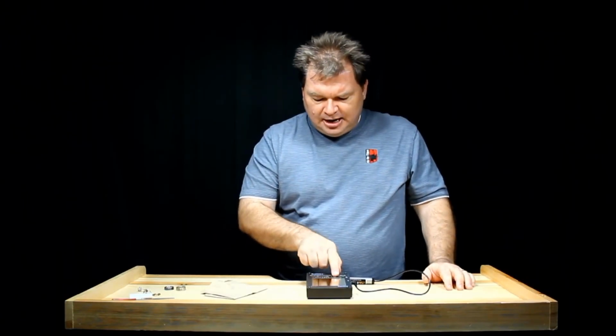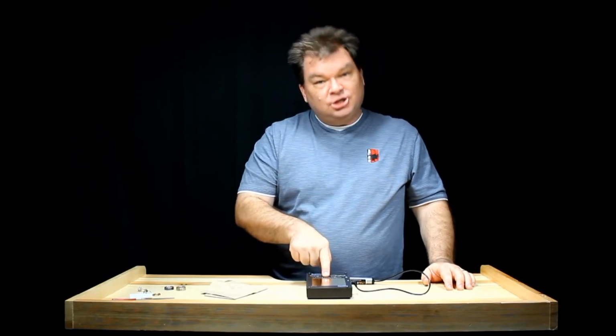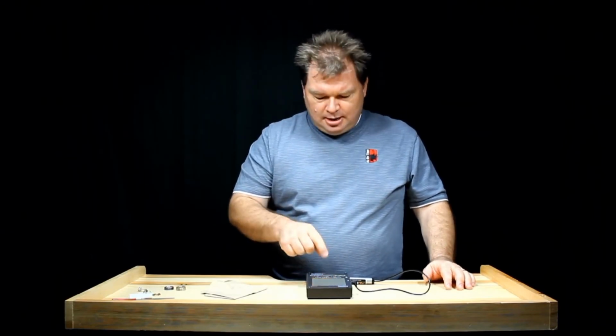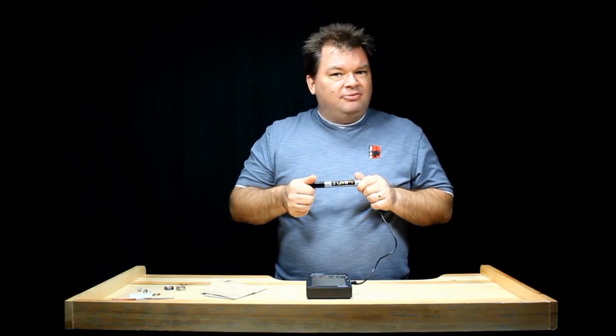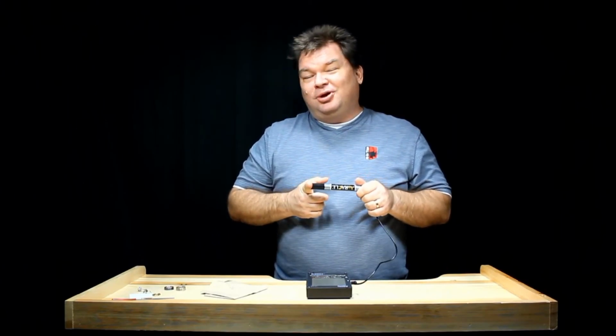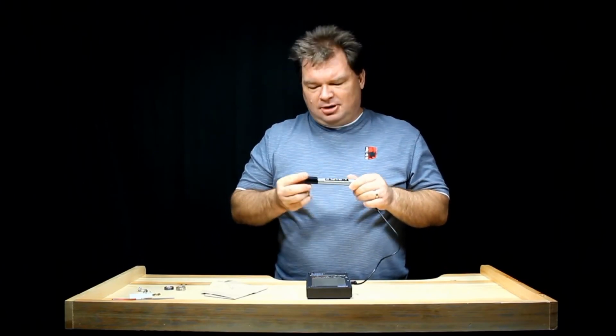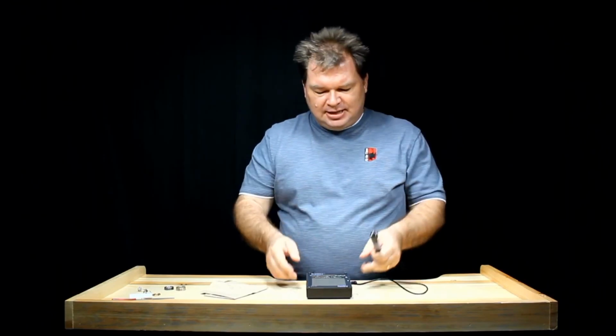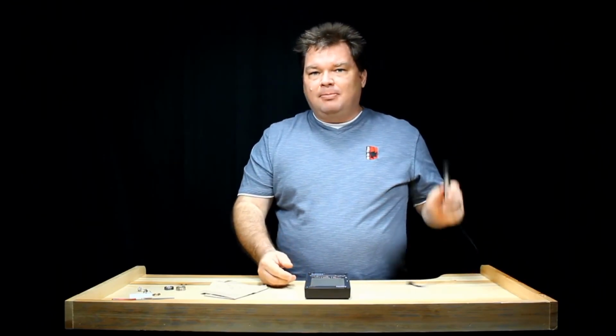Also, your indicator lights telling you to change your battery or change your testing probe should not be ignored. But the beauty of the tester is that this testing pen will give you over 5,000 tests with a single probe, and replacing it is as simple as unplugging it, purchasing a new one, and plugging it back in.